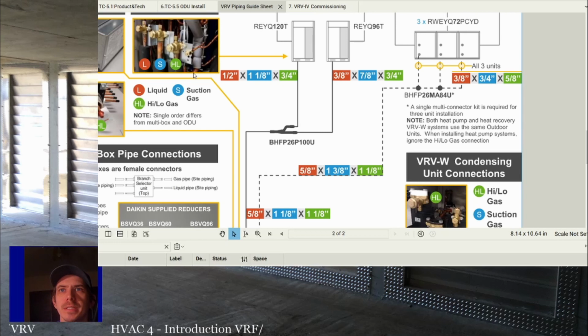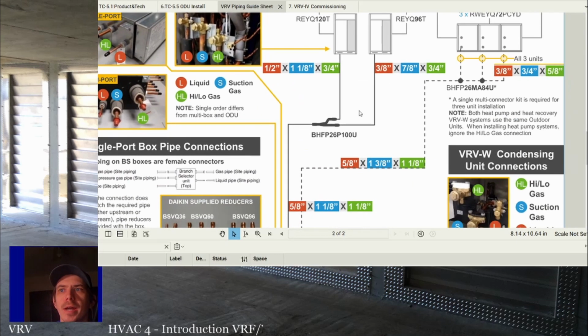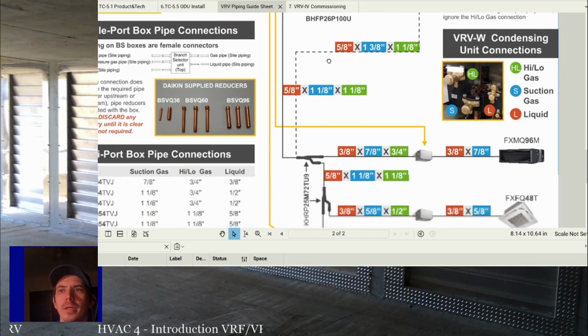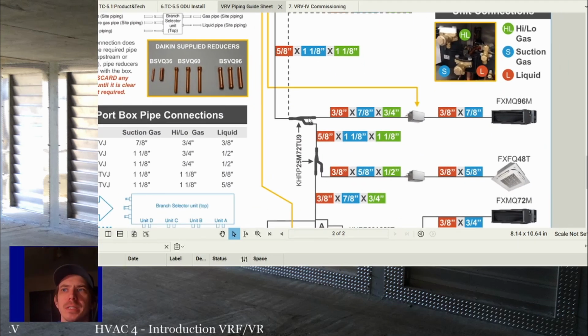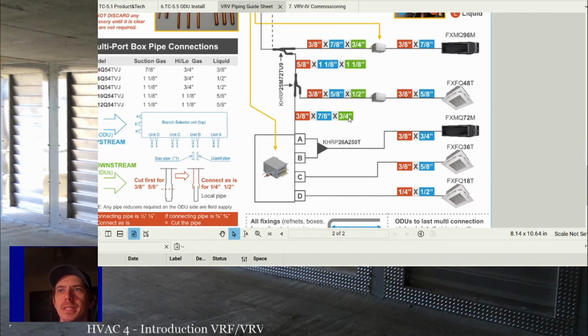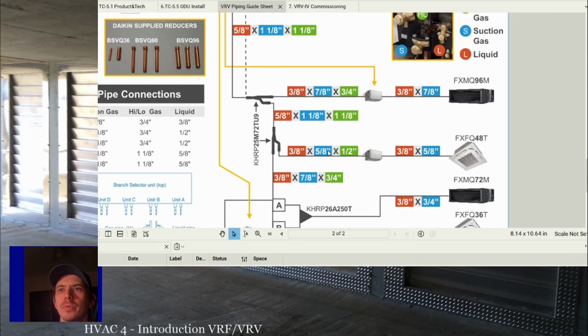So all three of these lines will be coming out of the unit and then they'll travel to where they need to go as a single set of three lines. So all these tie together at the outdoor unit. They continue, and then you get somewhere where you have to split. And you split with these special fittings. And, in this example, it splits right here. It splits 3/8 and 5/8, 7/8, an inch and an eighth, 3/4, an inch and an eighth. So this is basically your main line continuing.